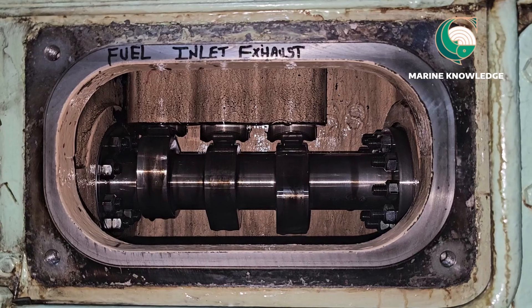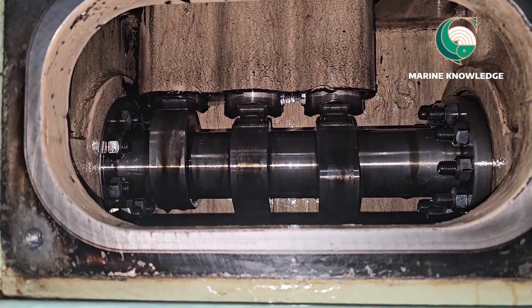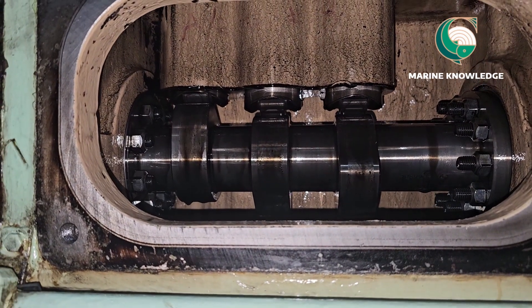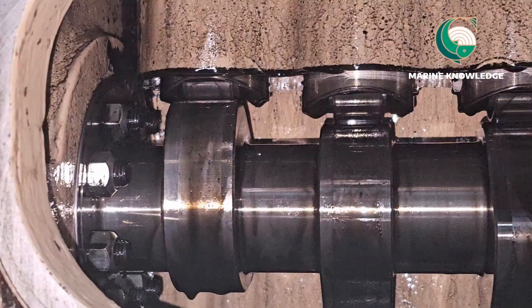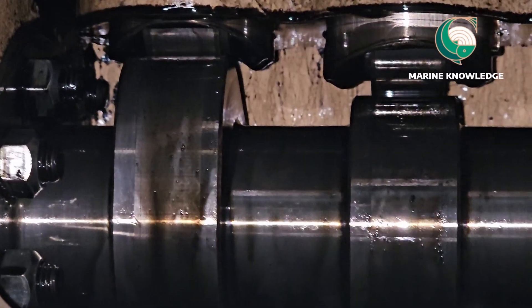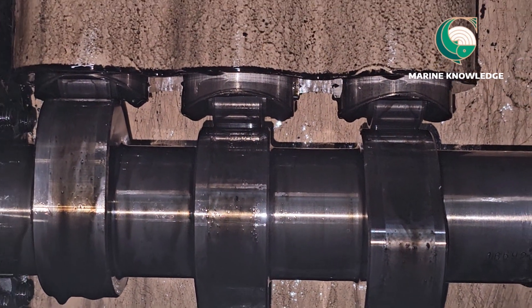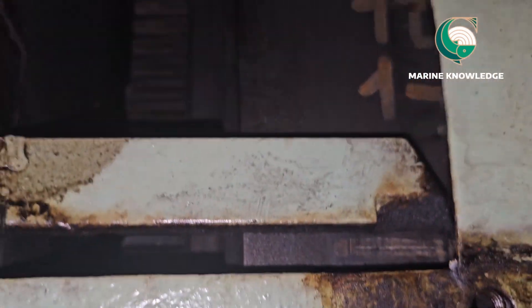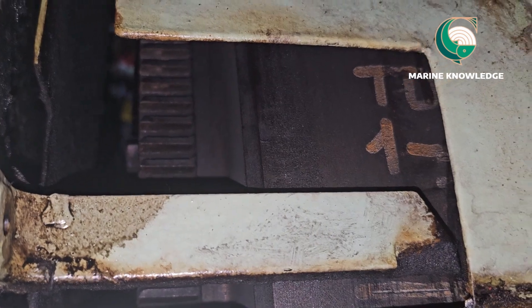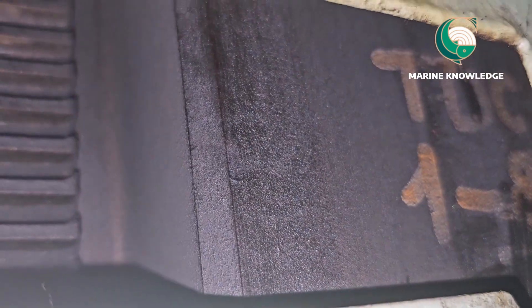So now we are going to adjust the tappet for this unit. You can see the cam for the fuel pump is about to reach peak — this is how you identify and confirm which unit is about to fire. You can see three cams: one is inlet, one is exhaust, and the corner one is the fuel pump cam. Accordingly, you go to the flywheel and see the flywheel marking to find out which units are at TDC.